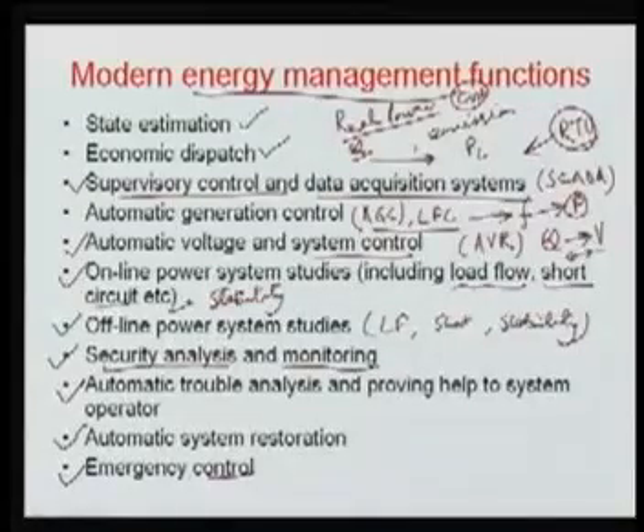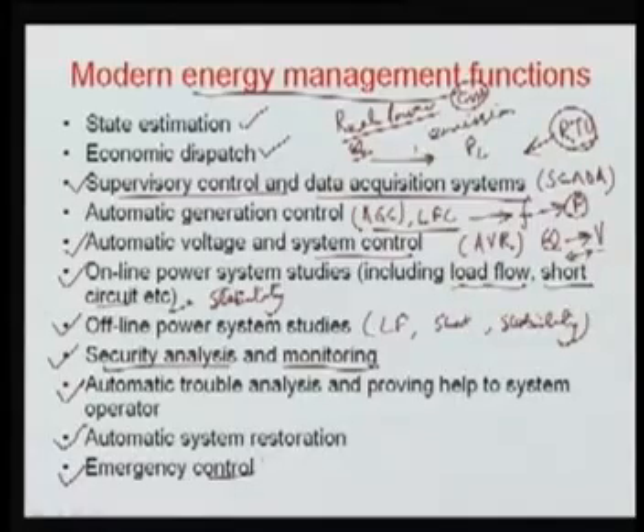The main intention of electricity operators is to provide supply to our customers with the least interruption. So we require emergency control functions whenever there is a problem, whether in a generating station or a substation, so that it does not lead to cascade tripping, which is called the collapse of the system. Emergency controls are always there in the power system, so that the operator can take those actions to maintain the complete system or part of the system and supply power in an economical, secure and uninterrupted way.